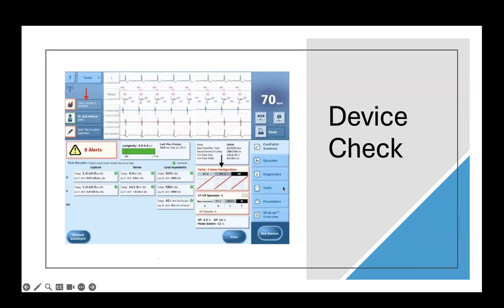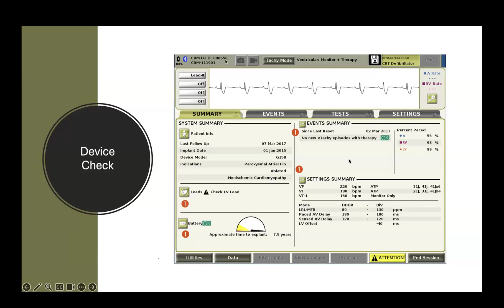However, you still have to go over the tests to check the general pacing parameters and to see if there are any issues with the device function before the surgery. So we checked this patient's ICD, and the sensing was appropriate. The P wave was around 2, the R wave was about 20. The atrial and ventricular lead thresholds were stable and comparable to baseline. The impedances were stable as well compared to baseline, so we turned the device therapies off.